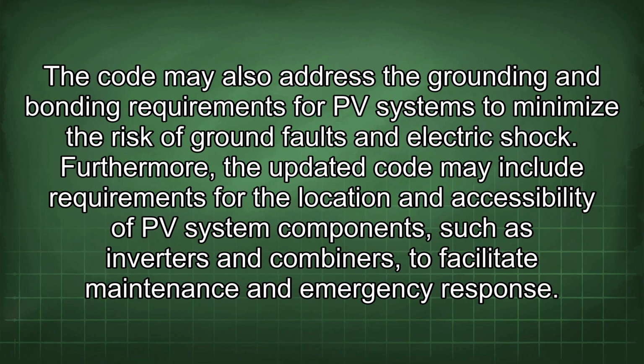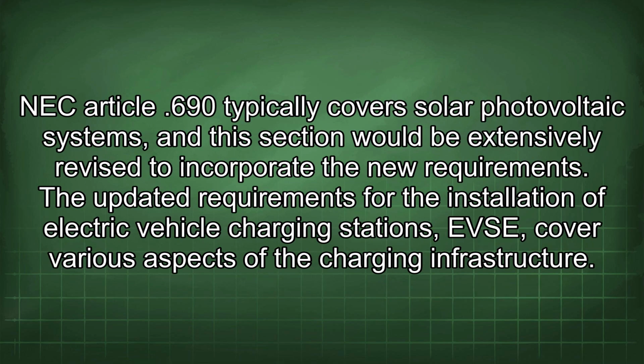The code may also address the grounding and bonding requirements for PV systems to minimize the risk of ground faults and electric shock. Furthermore, the updated code may include requirements for the location and accessibility of PV system components such as inverters and combiners to facilitate maintenance and emergency response. NEC Article 690 typically covers solar photovoltaic systems, and this section would be extensively revised to incorporate the new requirements.